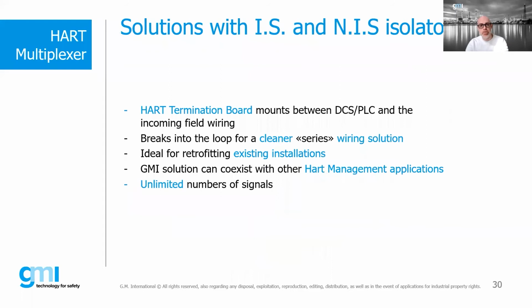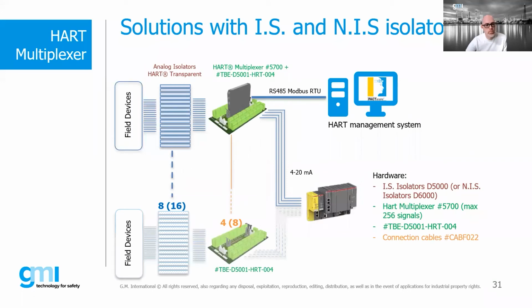Now let's see specifically the type of connection to be made in the different solutions proposed. Let's start with the solution that uses barriers or isolators mounted on the rail. In this case, we will use the model TBE D5001 HRT004 terminal block HART termination board. The aforementioned termination board is inserted in series with the 4-20 milliamp loop and is the ideal solution for implementing HART in an existing loop. Well, Andrea, do you want to explain the next slide? Yeah. This slide gives you a better idea of how you can integrate the HART multiplexer in existing loops, where you have the input and output boards.